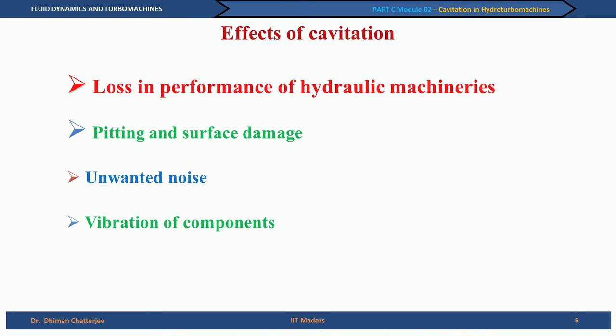So, the second point is about pitting and surface damage. Now, I will show you one pump impeller to bring out what cavitation can do. You will see in these impellers that small holes are being made, as if somebody has taken out the material very minutely. So, let us look at that impeller in more detail.